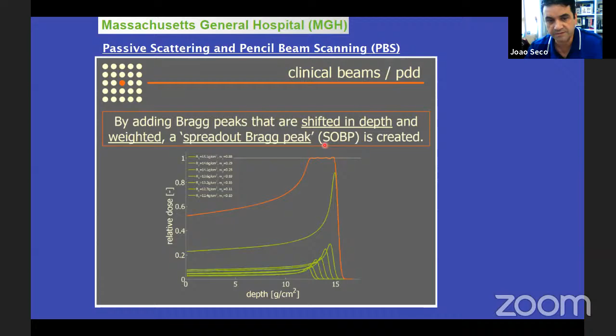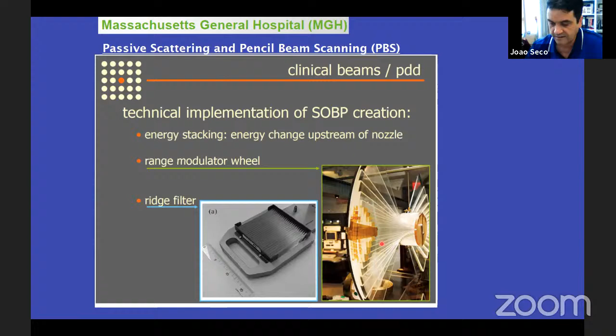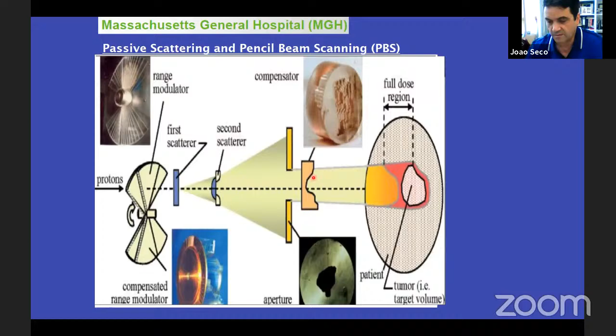So here is an SOBP that is produced, for example, with a passive scattering system. I have multiple Bragg peaks put together, different levels, and they produce a flat region here, which is used for treatment. In that case, the SOBP can be produced with the ridge filter, which is what we have here in Heidelberg, or the range modulator system that is at MGH. And you see the steps of this plastic. Each step is approximately 3 millimeters of absorption. So 3, 6, 9, 12, and so on. So you can absorb up to as much as, not 100 centimeters, sorry, 20 centimeters in depth. So the range modulator is this part. Pay attention that this is usually done with a narrow beam. You have your double scattering systems that broaden the beam, and then you have your compensator.